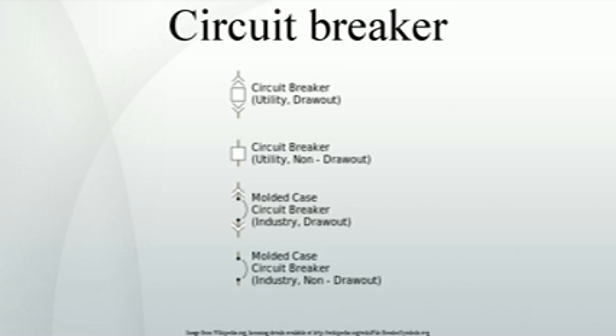The trip solenoid that releases the latch is usually energized by a separate battery, although some high-voltage circuit breakers are self-contained with current transformers, protective relays and an internal control power source. Once a fault is detected, contacts within the circuit breaker must open to interrupt the circuit. Some mechanically stored energy, using something such as springs or compressed air, contained within the breaker is used to separate the contacts, although some of the energy required may be obtained from the fault current itself.